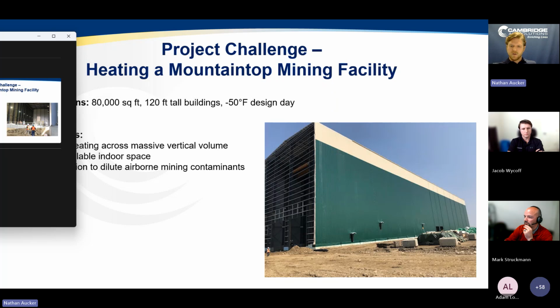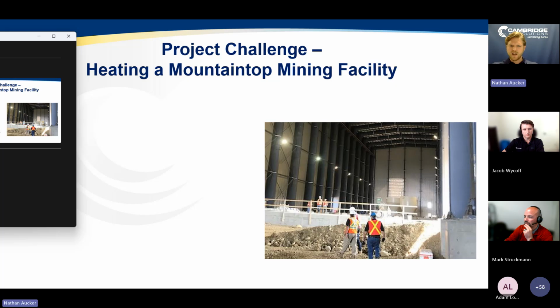There's a large volume, and really this is a mining facility, Bighorn Mining. They're trying to also reduce contaminants in the air. They want to de-stratify the space. They really don't want to just be heating the top end of the space, of course. So designing a system for this facility, it's important to address both the heating and ventilation needs. So those are considerations. They had 3 buildings in this particular opportunity.